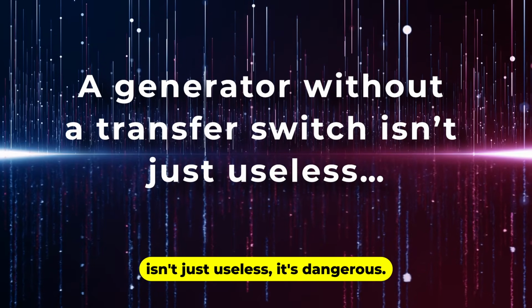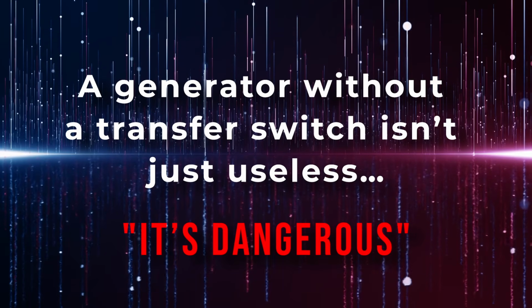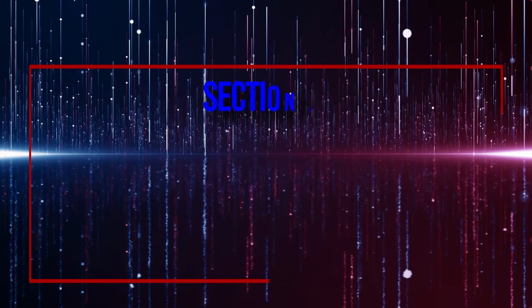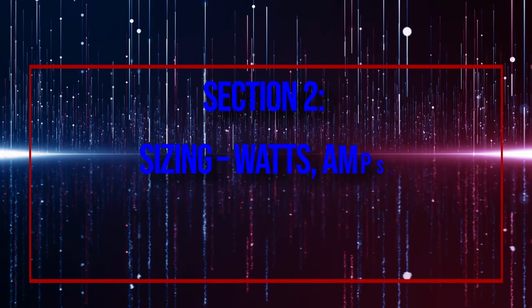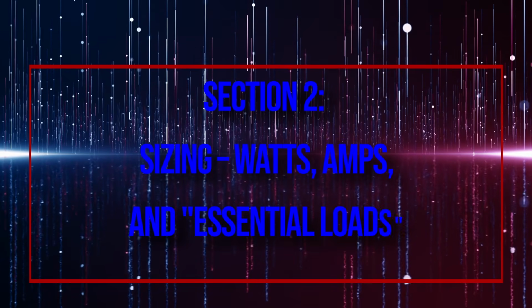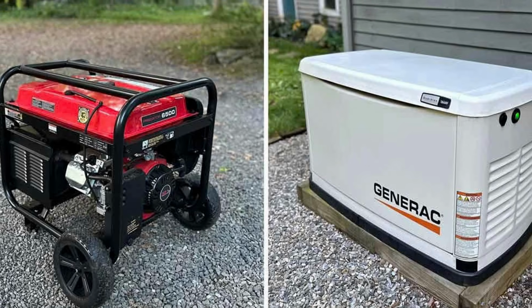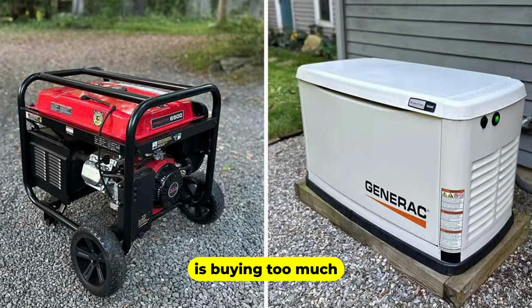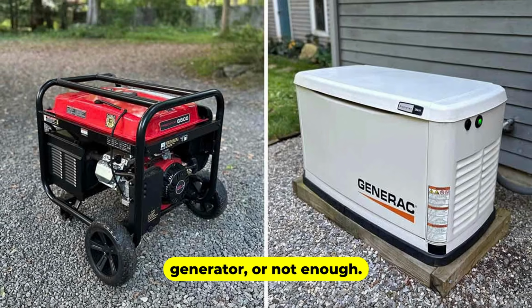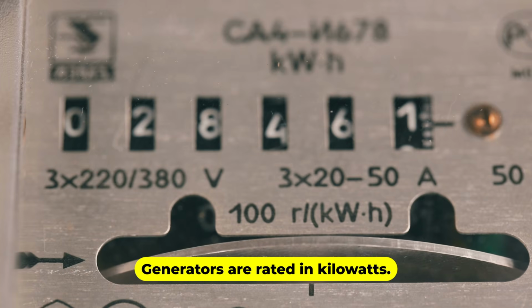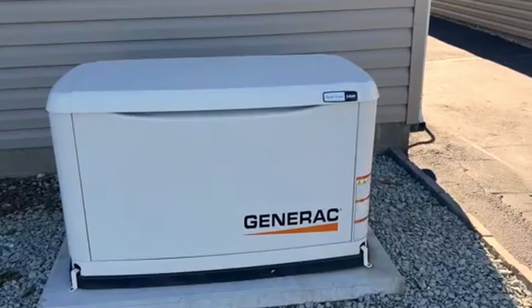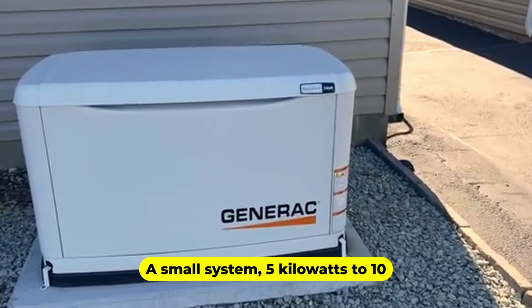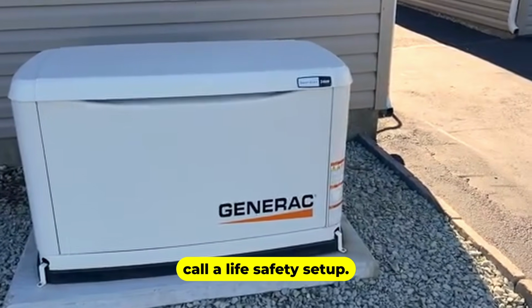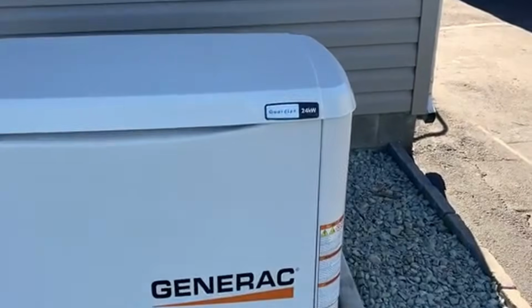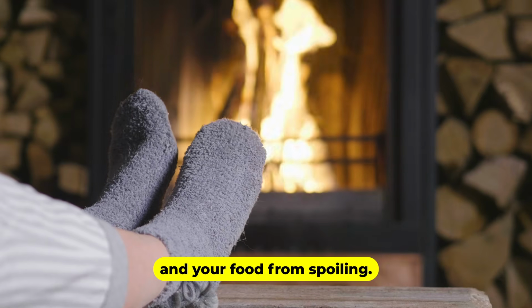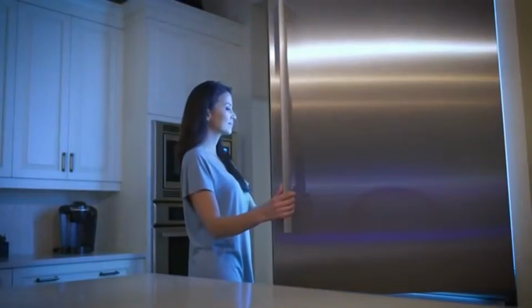Section 2. Sizing, watts, amps, and essential loads. One of the biggest mistakes people make is buying too much generator, or not enough. Generators are rated in kilowatts. A small system, 5 kilowatts to 10 kilowatts, is what we call a life safety setup. It's designed to keep you from freezing and your food from spoiling. It handles your furnace, your fridge, and maybe your internet router.